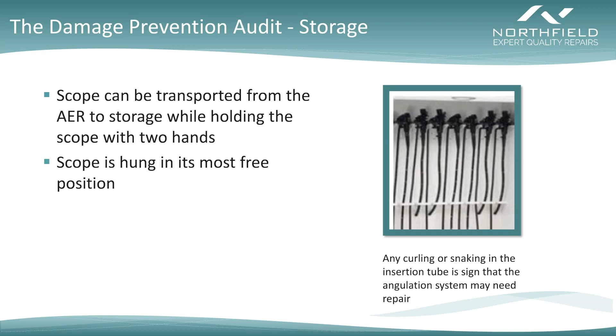Now, like we said, we want to make sure that the scope can be transported to and from the automatic endoscope reprocessor properly. That means two hands. And when we hang it in the cabinet, we want to make sure that it's still in its most free position. So make sure that angulation locks are still in the free position. The tensioner is still in its most free position. Anytime you see scopes that are kind of hanging with curled tips, or maybe even seeing what we call snaking, where that insertion tube kind of bends back and forth on its way down, that's an early warning sign that your scope has something going on inside of it. Even if the OR hasn't complained yet, even if the doctor hasn't complained yet, that is telling you this scope is in danger. It's about to break at some point in the near future. So if you see that snaking, you know you've got a problem, and you know that you need to go ahead and get those scopes sent out as quickly as possible.